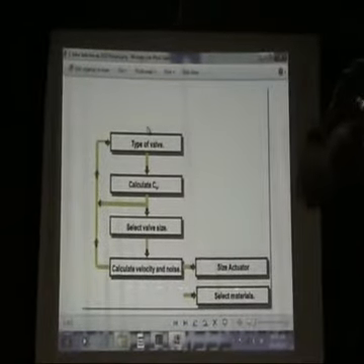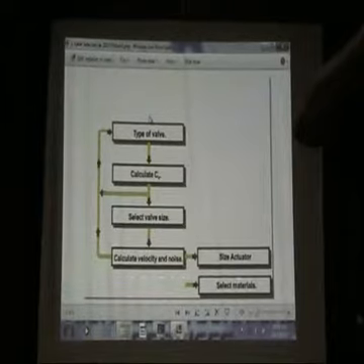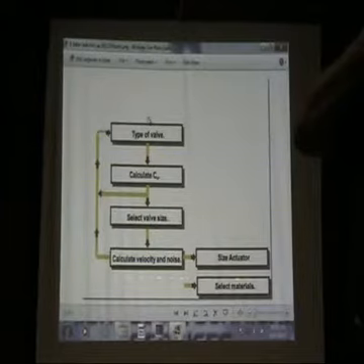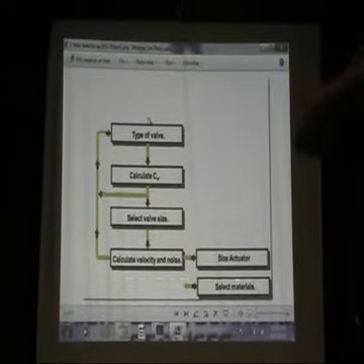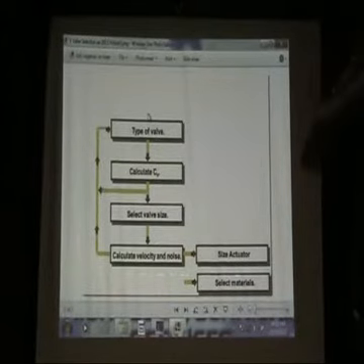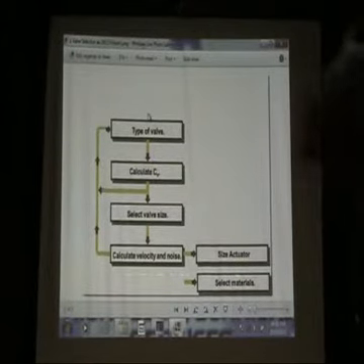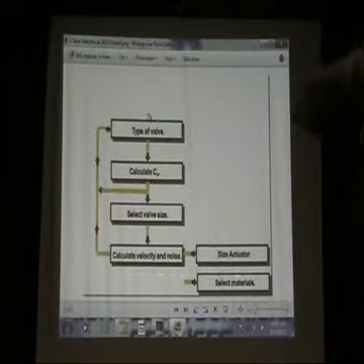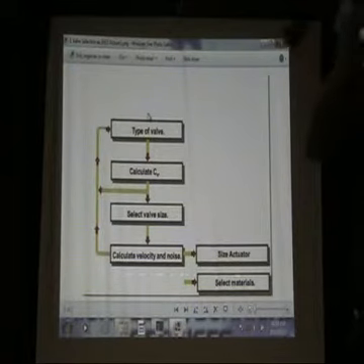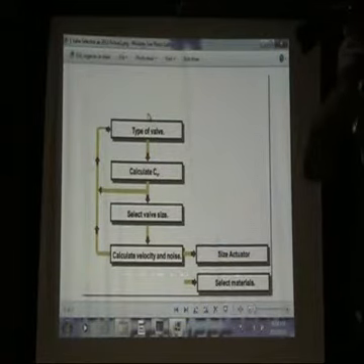Okay. The other thing is, the guys got cleverer. Years ago there were specs written around valves, but as the technology improved, the specs weren't adapted to that, so the specs have changed. These days you can get this 15 bar rated. So you get 10 bar rubber lined butterflies and you get 15 bar. That's about the maximum these can do. With this soft rubber lined butterfly, you can change the liner, they call it EPDM or natural rubber. It can handle about 80 degrees maximum.